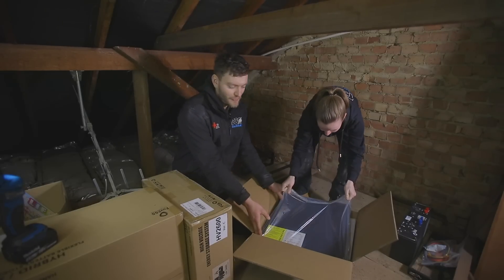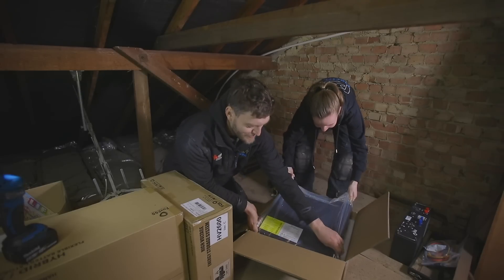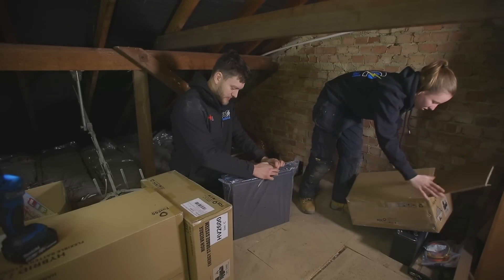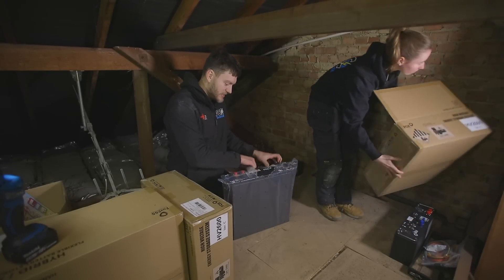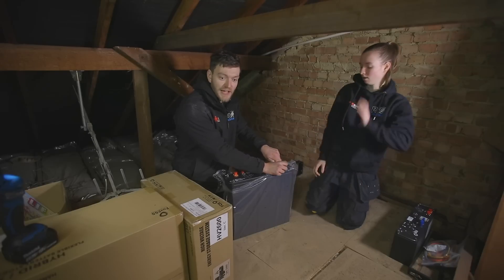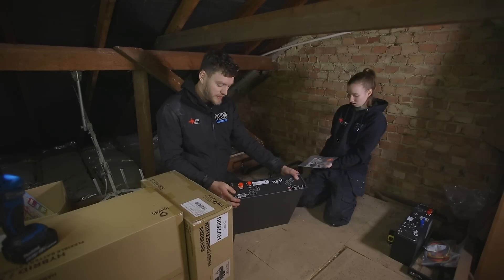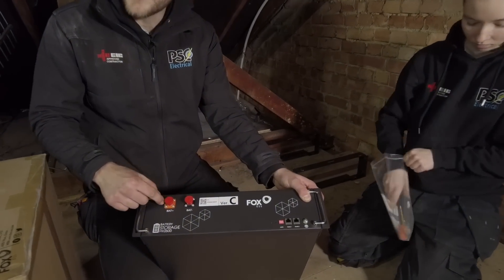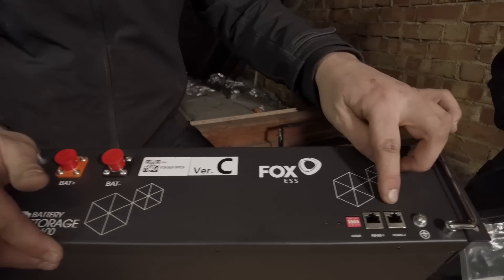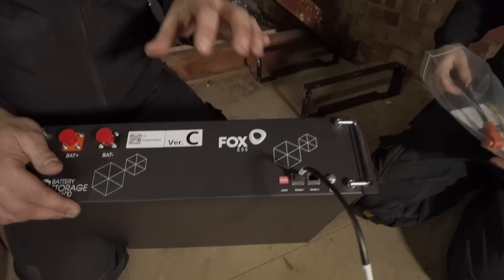Here we have one of the battery modules which is very heavy, so ensure that when you lift them up you have two people to help. Inside here is a lithium battery. These batteries will plug directly into each other. Because it's a stackable system it means you can add batteries after a job if you require more capacity. On the front of the battery we have our two negative and positive ports — these will get plugged into the battery above or below. We also have ethernet ports which link the different battery modules so that they're talking to each other via the app.